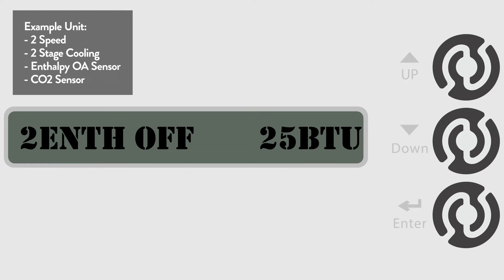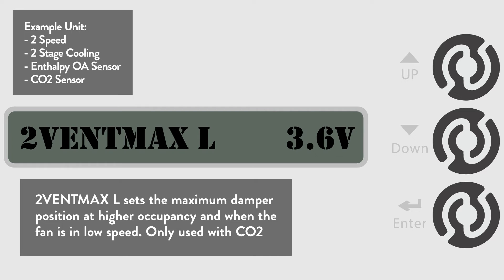The next several screens deal with CO2 sensors. In the 5 configuration state, we told the controller we had a CO2 sensor and set the sensor voltage. These next adjustments will set the minimum and maximum damper position settings for the controller when not in free cooling. These settings are made by adjusting the voltage to the economizer actuator. Since we have a 2-speed unit, we have a minimum and maximum position damper setting for both low and high speed. Go to the 2 Vent Max L menu to set the CO2 sensor's maximum non-free cooling position when the unit is in low speed. The default is 3.6 volts, but let's change that to 3.4 volts.